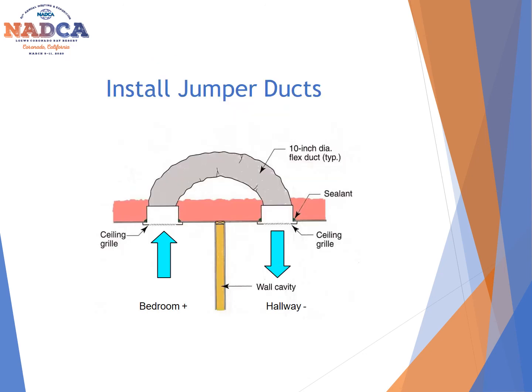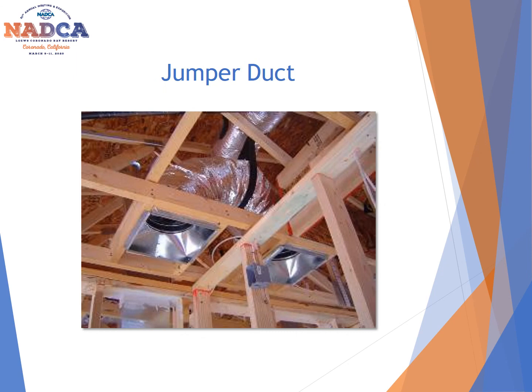So one way that you can actually rectify this situation is by creating jumper ducts. And they're not actually ducts connected to your HVAC system. What they are is actually just connected to the 2 rooms. So if you have a hallway, like in this picture here, and you have a doorway that's shut, what it does is it allows that air to easily flow from the bedroom on the left to the hallway on the right. So if you come across a house and you happen to see one, this is what it would look like. You can actually see in this picture here, it literally just goes up into the attic and back down again on the other side. It's that simple, and it helps to improve the airflow between the 2 areas.